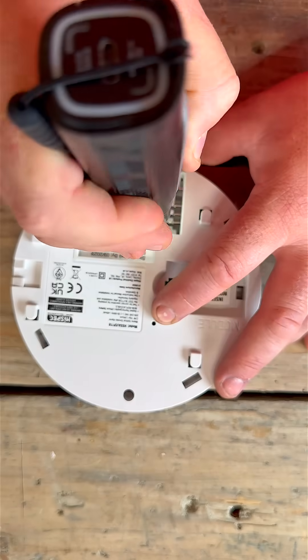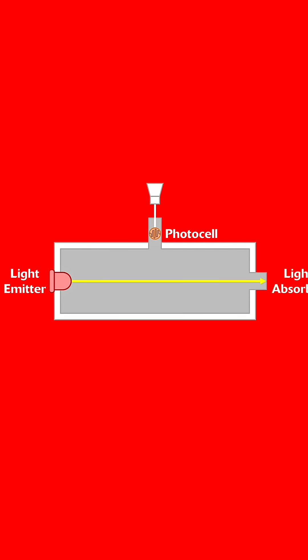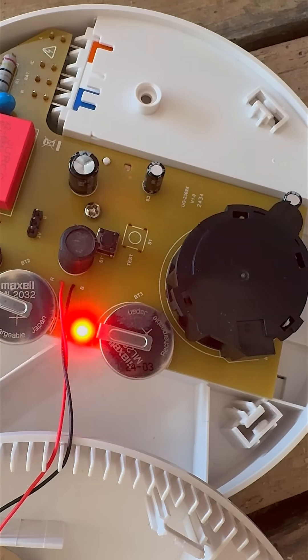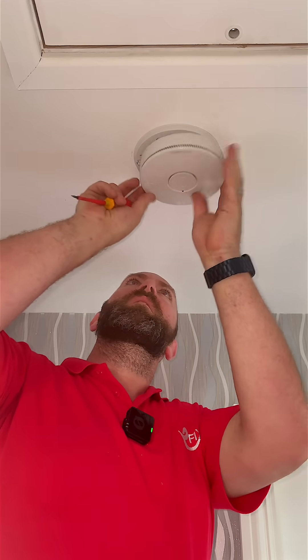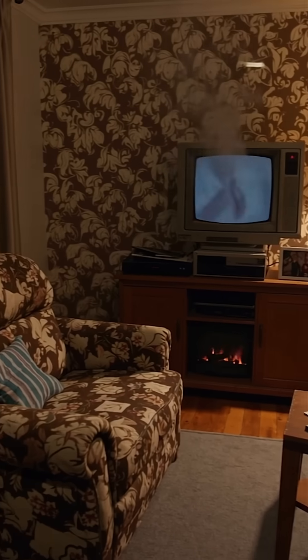Let's take these detectors apart and see what we can find inside. A smoke detector, especially an optical type, works by using a light beam inside a sensing chamber. When smoke enters the chamber, it scatters the light beam, triggering the alarm. This makes it highly sensitive to slow, smoldering fires like those caused by overloaded sockets or faulty wiring. They're ideal for hallways, bedrooms and living spaces — anywhere you want fast detection and minimal disruption.